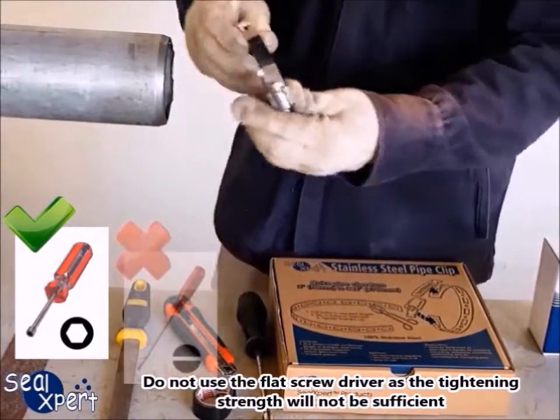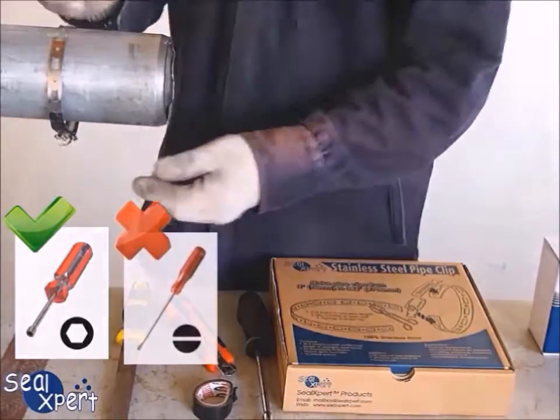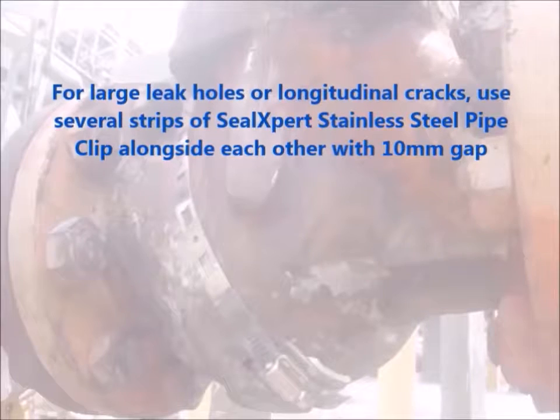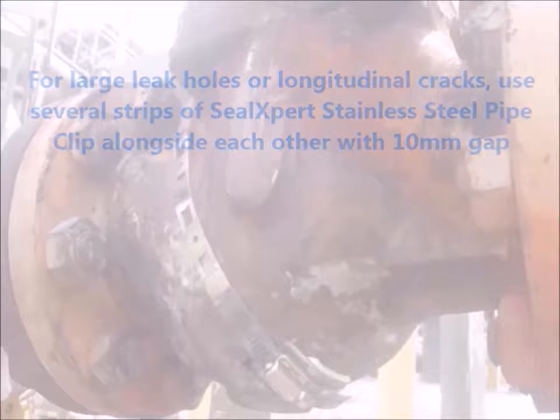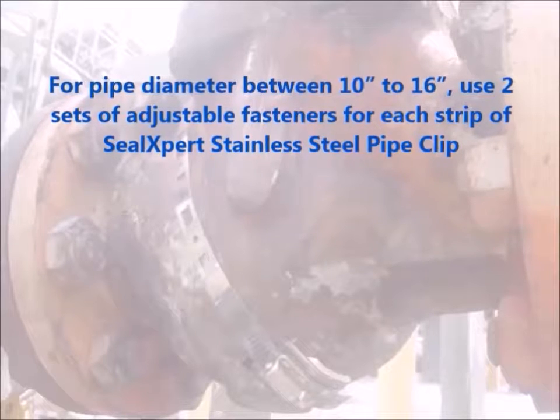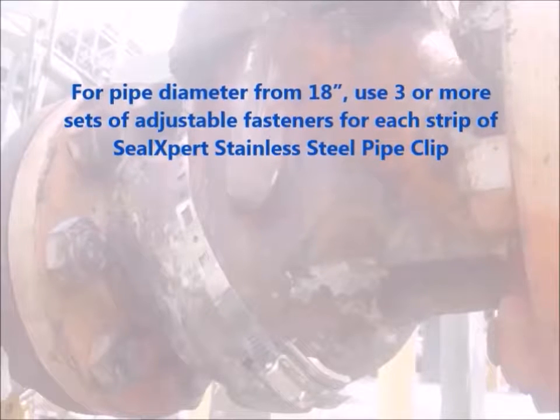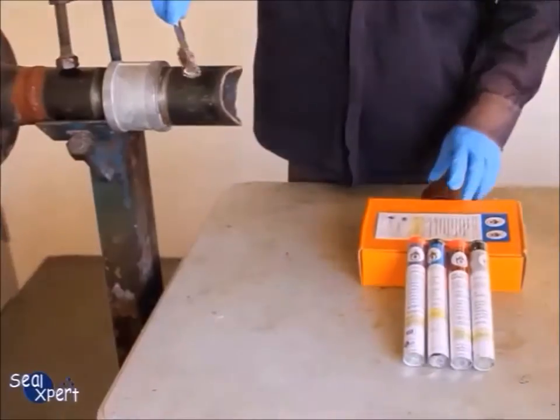For large leak holes or longitudinal cracks, use several strips of SealXpert stainless steel pipe clip alongside each other with a 10-millimeter gap. For pipe diameter between 10 inches and 16 inches, use two sets of adjustable fasteners for each strip. For pipe diameter from 18 inches, use three or more sets of adjustable fasteners for each strip.